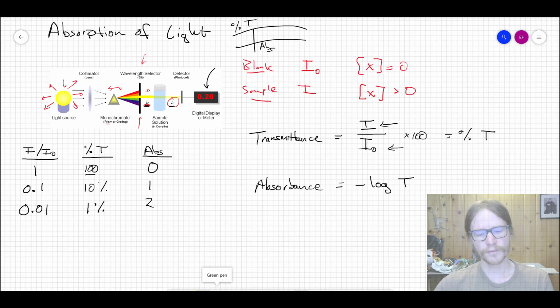And so often, and you probably have heard this before if you've taken other courses that use absorbance a lot, especially biochem, we say for most spectrometers, we don't accept measurements in excess of 2. Some modern spectrometer detectors can maybe get up to 3 in a reasonable way, which would account for 0.1% of the light. But imagine, right? You have this bright light, all this signal, and then you only have a trickle of it hitting your detector. You have to have a really incredible detector to be able to reasonably measure only 0.1% of all of the light and still do that in a linear way.